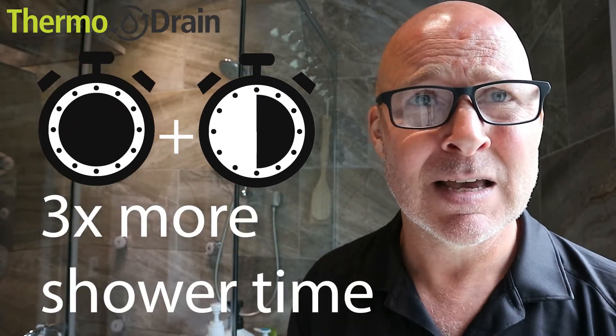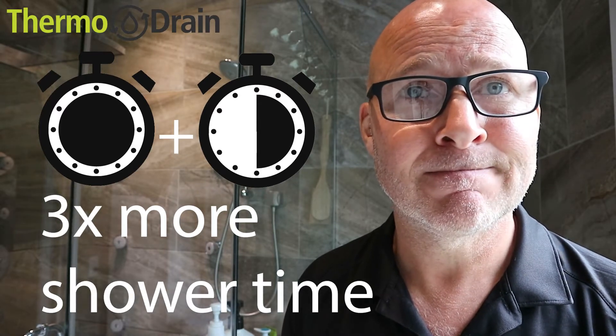If you have a tank or tankless gas or electric powered hot water heater and you combine it with a drain water heat recovery system, you can without a doubt get way more hot water out of that same system, plus you will save on energy costs associated with recycling that energy. The Canadian Centre for Housing Technology took a 40-gallon hot water tank and ran a shower continuously until it ran out of hot water — they were able to run that shower for 28 minutes. What if they combined that with a ThermoDrain unit? They did that, and they found they were able to get three times more hot water off of that tank system using a ThermoDrain. Amazing!